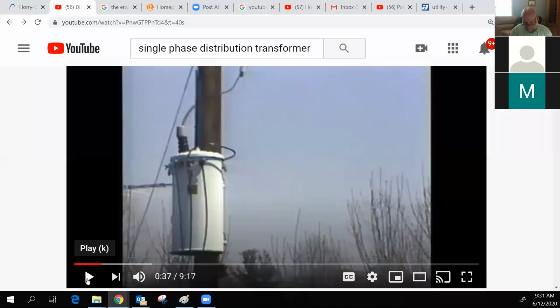Only has one bushing. One bushing, that's right. Just like on the transformers on the poles out on the yard that you guys have been changing around, if you look at the bottom right, you'll see a little lug near the bottom of the tank with a piece of wire coming off of it. Just like the transformer we looked at in the field where it comes in one bushing, goes through the coil, and comes out the top. Down at the bottom on that tank ground is the other end of that winding. Instead of coming out on the bushing, it actually comes out on that tank ground and bonds to the pole. That's really no difference. You get the same voltage out that you do with a two bushing transformer.